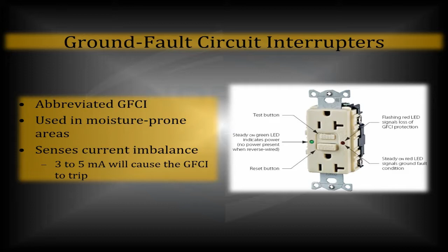Now, if I become that circuit and I hold on to the hot leg and the neutral leg, and the circuit just goes straight through me and on back to the source, I may not change the incoming and exiting amp draw, so it won't trip. And that's why it can't be the primary life-saving device. It is a life-saving device, secondarily, when you're talking about where it's located and how it's supposed to act. But these things are very interesting, and that's why you're going to see them all over in a house. And that's a requirement by code. It's easily said now that any place in a home that's not GFCI protected is going to be arc fault protected.